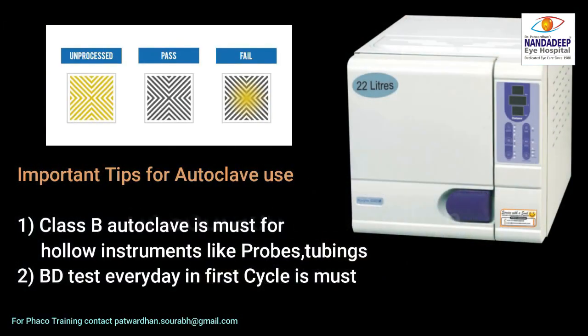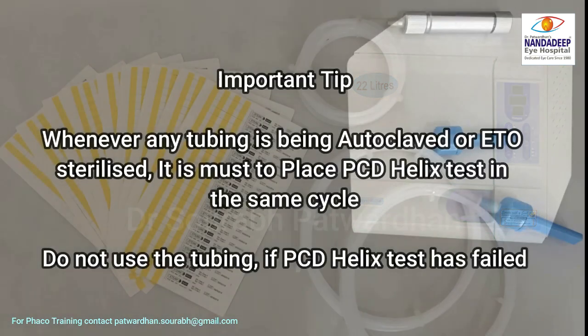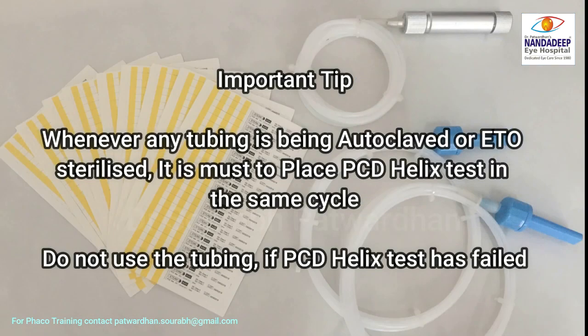A few things often missed: always use a class B autoclave with multiple pre-vacuum cycles for hollow instruments. The BD test must be done every day in the first cycle to confirm the equipment is functioning properly. Another important but frequently overlooked test is the PCD helix test, where a tube is placed with the indicator at one end alongside any tube you want to ETO or autoclave. Only if this test has passed should that tube be used.